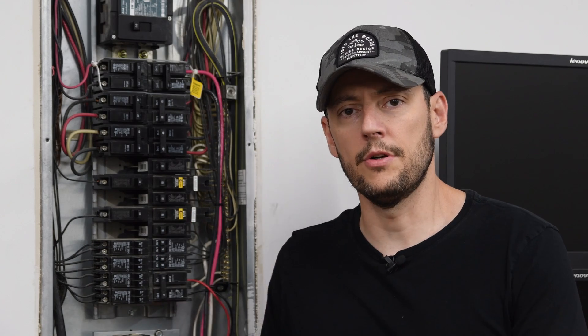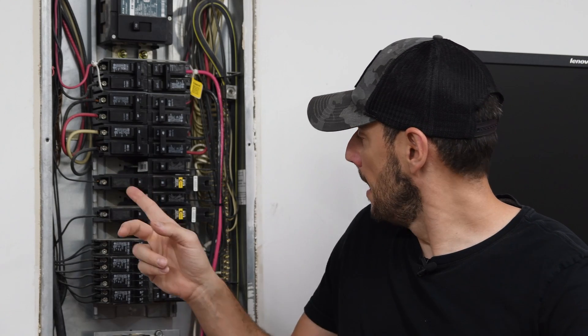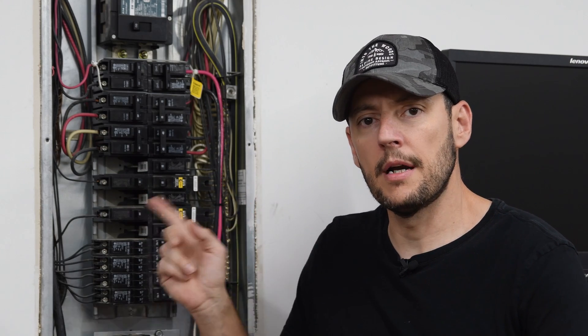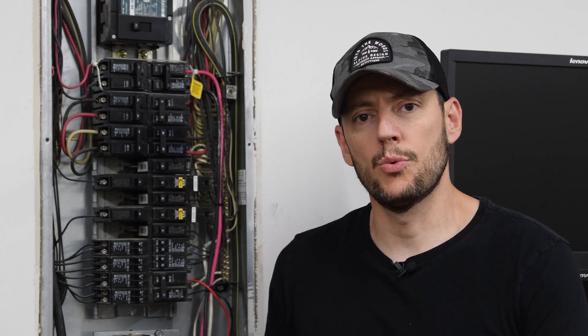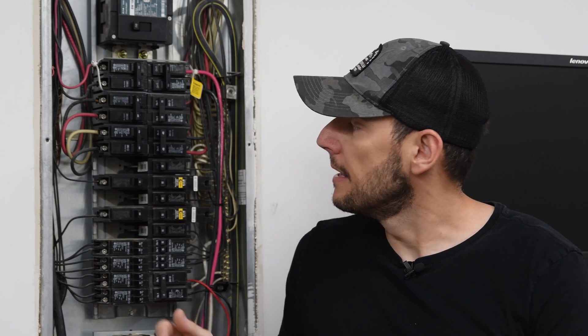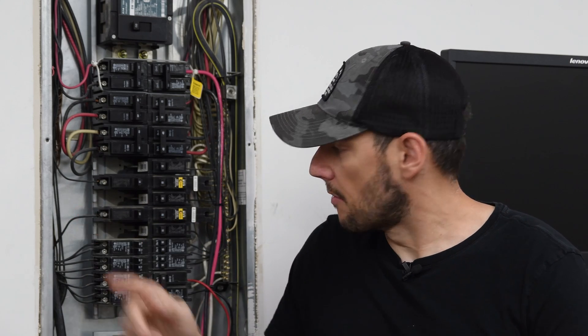If you look inside your breaker panel, you're going to see that the ground bar and the neutral bar are connected together. That is what is called a neutral bonded system, meaning that the neutral is bonded to the ground bar.